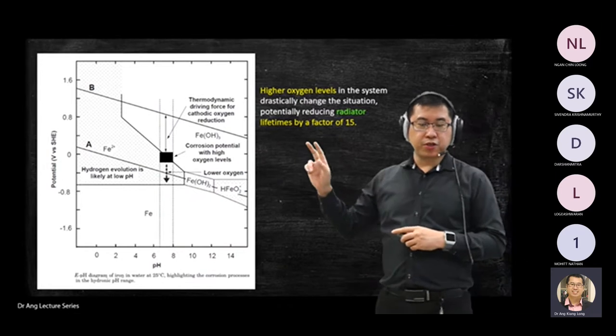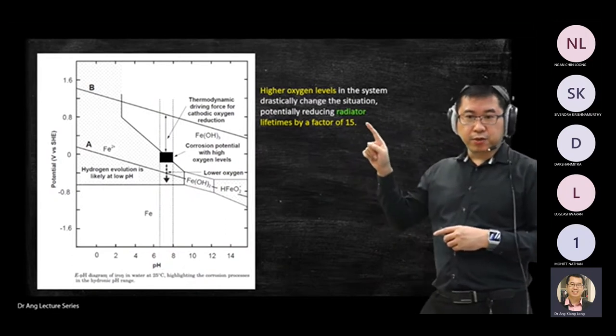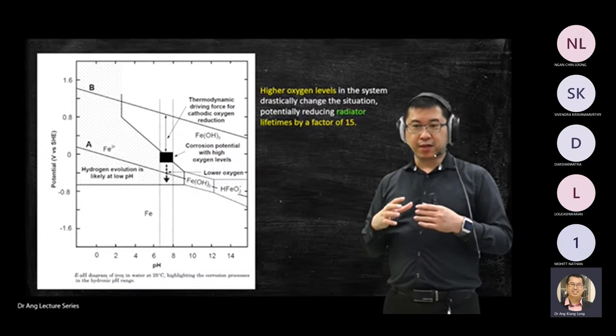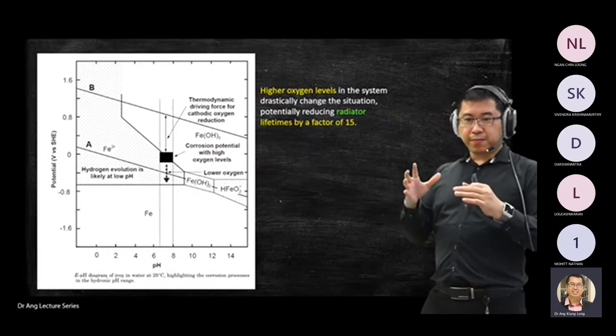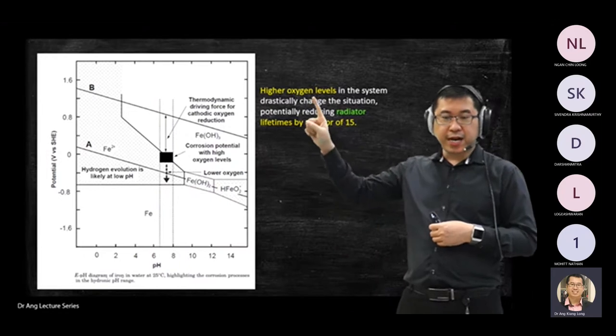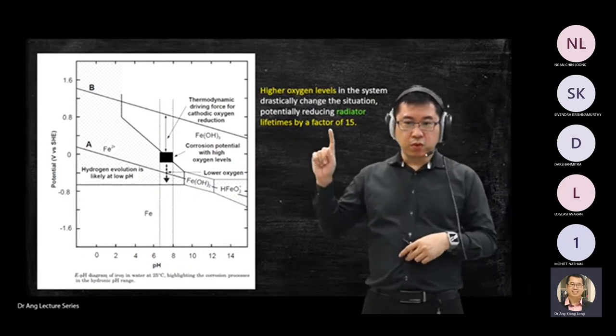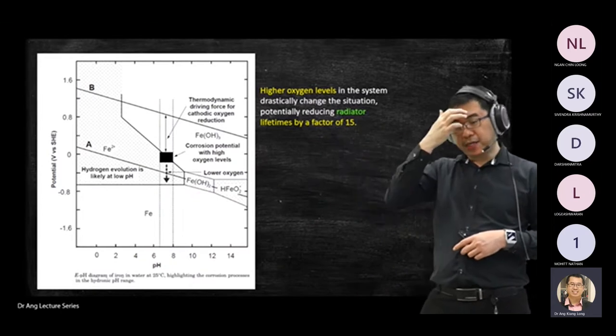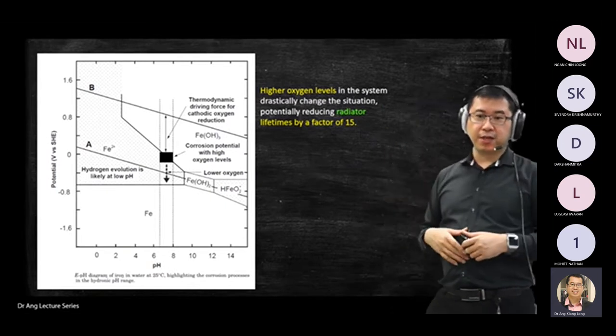This slide is about the oxygen level. There has been a study: if you are using a radiator with very high oxygen in the system, the lifetime will reduce by a factor of 15. You don't need to memorize the number, but highlight the effect: if you increase the oxygen level in the system, corrosion increases.